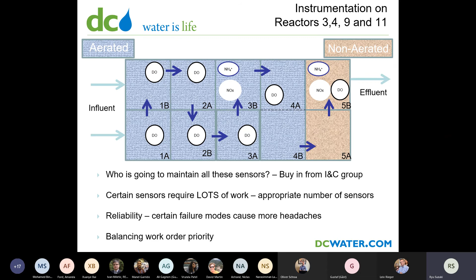So originally we had the basic DO control mode, where you have your target DO set point, and there's a PID. It's actually more of just a proportional integral controller that sets the target airflow. Based on the target airflow and the measured process airflow, there's another PID loop that sets the air valve position. So this is all the odd side reactors. Each one of these control valves has a fully independent DO loop. And overall, the DO loop controllers do work well in meeting our process target.